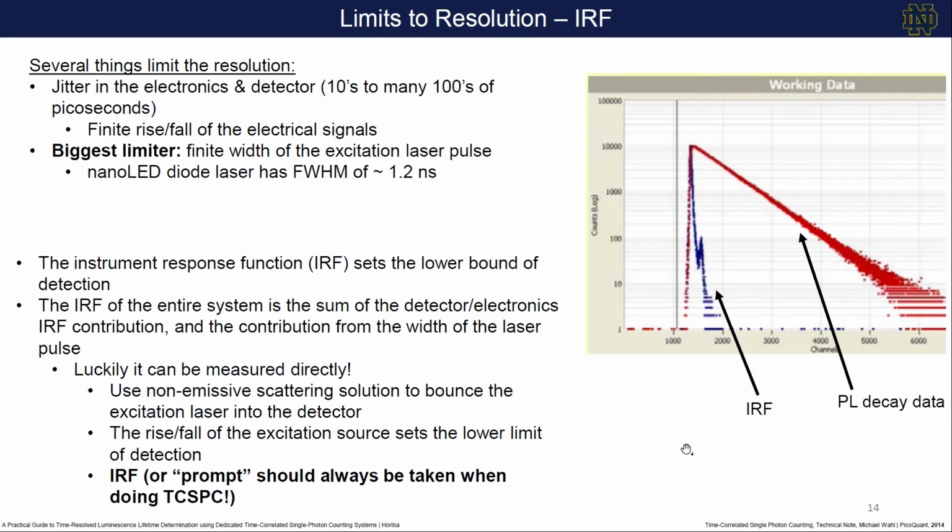And so this is essentially the IRF of the system. Oftentimes, at least in our case, the software calls it the prompt, but prompt and IRF are basically the same thing. But it is extremely important to always remember to take the prompt or the IRF whenever you do TCSPC, because you not only want to see how your material is decaying, but also how close it is to the response of the actual system.